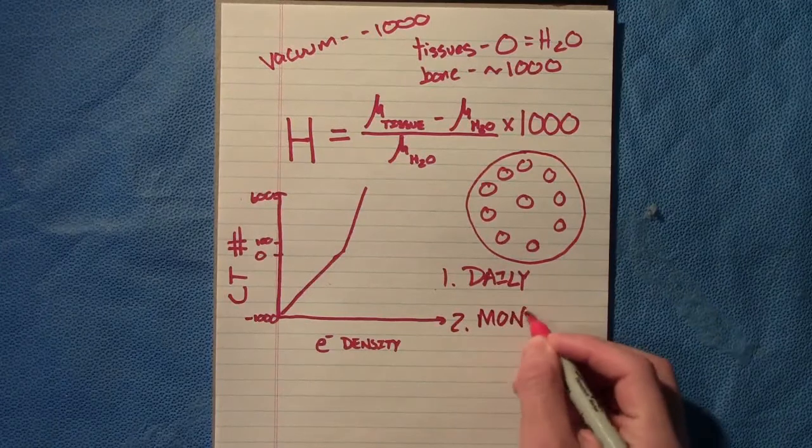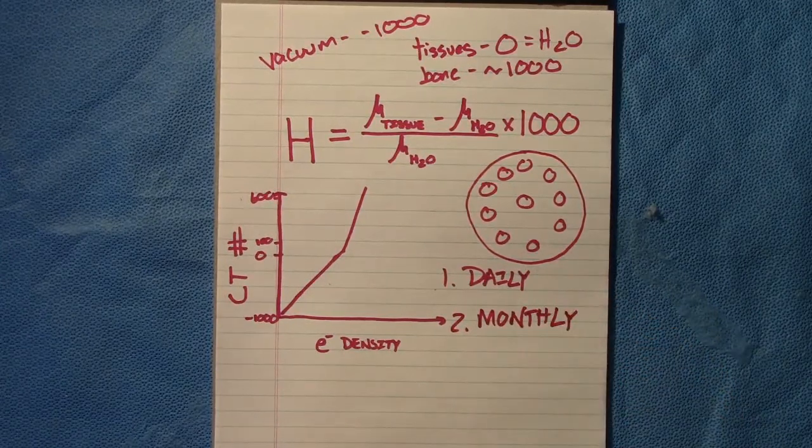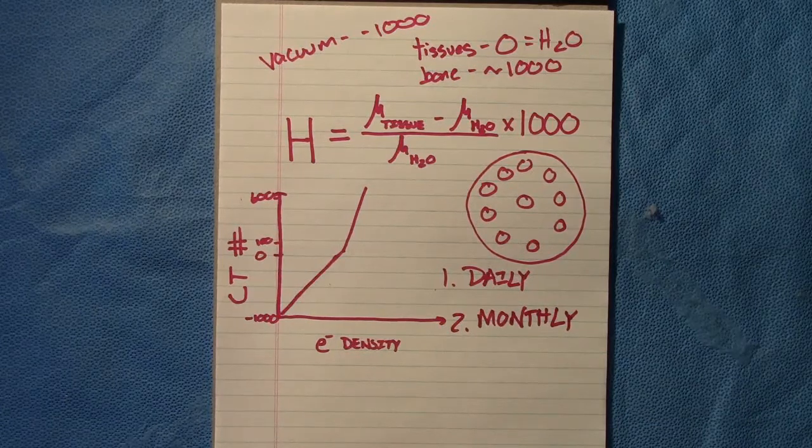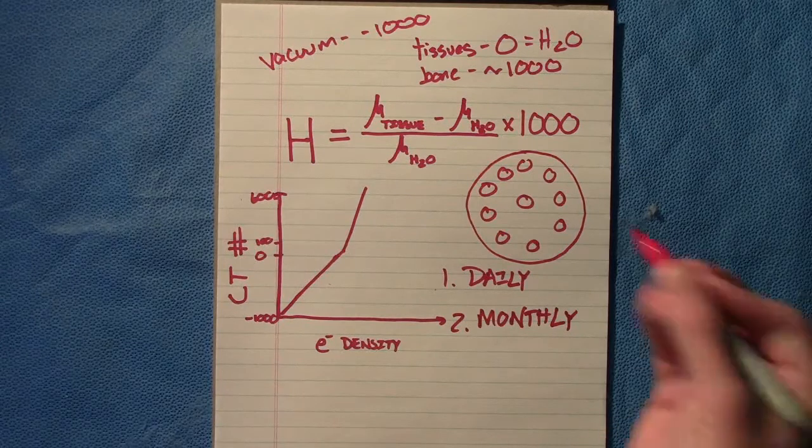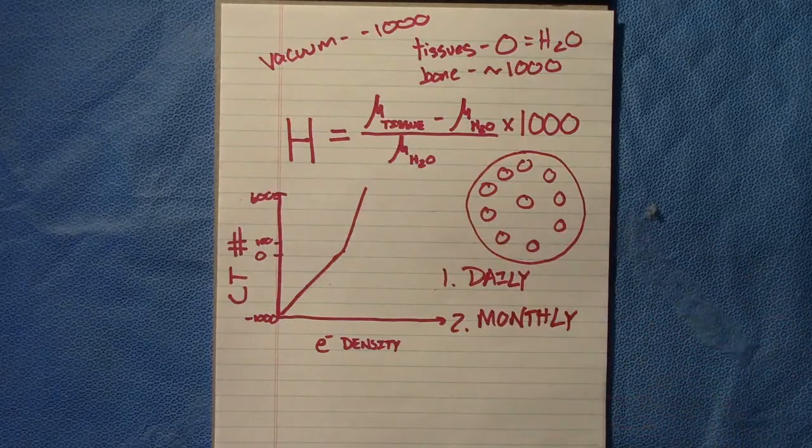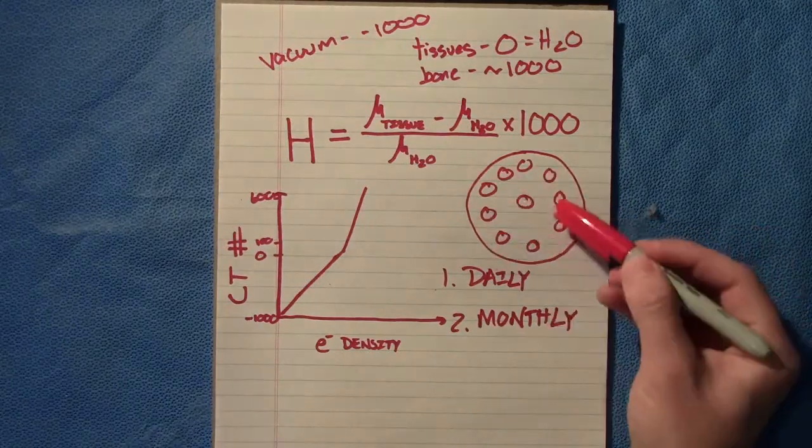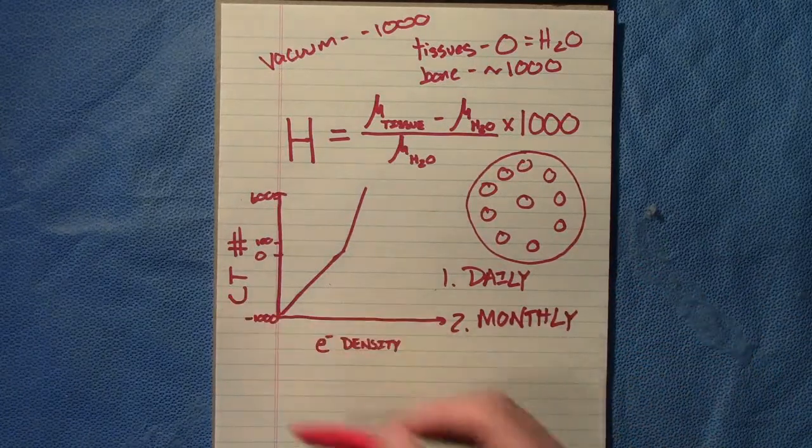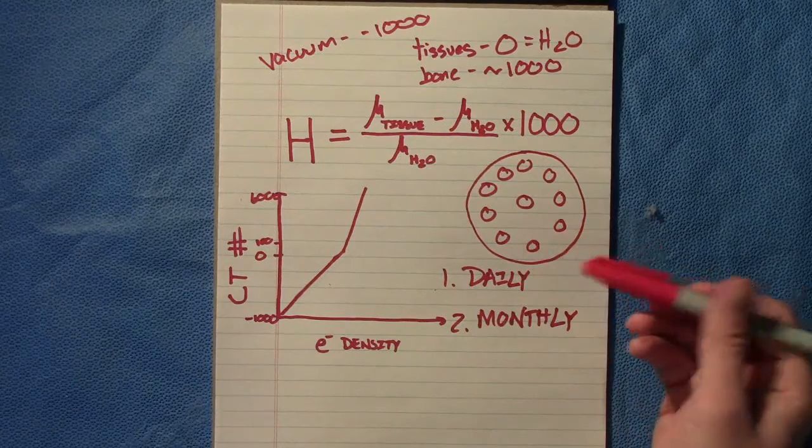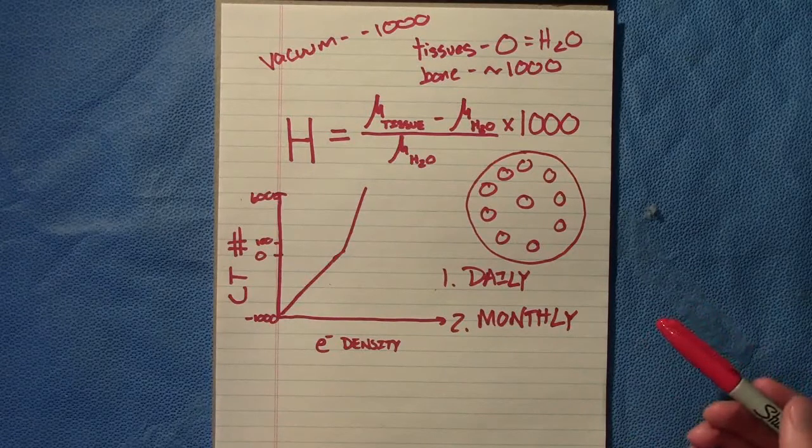Second, we also do a monthly, and that is a more exhaustive daily QA essentially. We scan a phantom, we import it into the treatment planning system, we verify that the CT number for water is zero plus or minus 10, acrylic, PMMA, bone—all these things. We verify that the treatment planning system and the CT are assigning that correct CT number to a certain range, because CTs over time potentially may read it differently. They're complex machines, and you may need service if it's starting to drift for CT numbers.